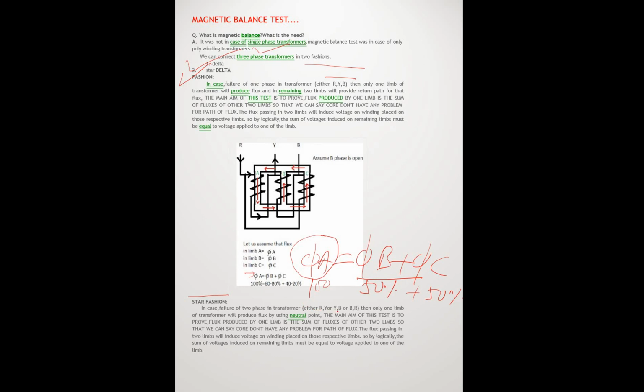two phases in a transformer, either R and Y, or Y and B, or B and R. Then only one limb of the transformer will produce flux by using the neutral point, and the main aim of this test is to show flux in one limb and the sum of the fluxes in the other two limbs. Okay, and the two limbs will induce voltage on the windings on these respective limbs. So logically the sum of the voltages induced on the remaining limbs must be equal to the voltage applied in one limb, equal to the sum of the remaining limbs.